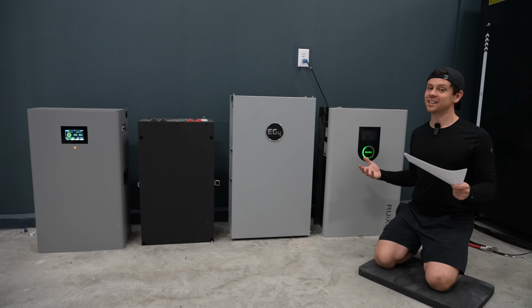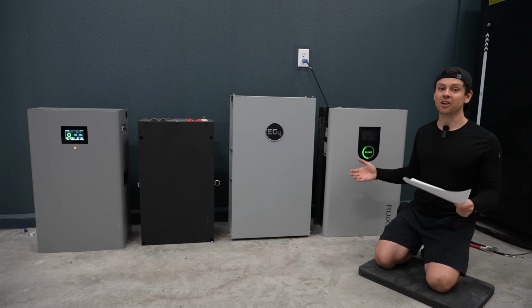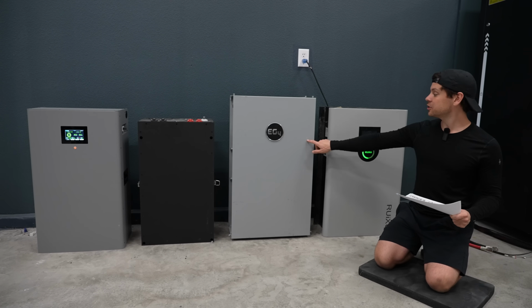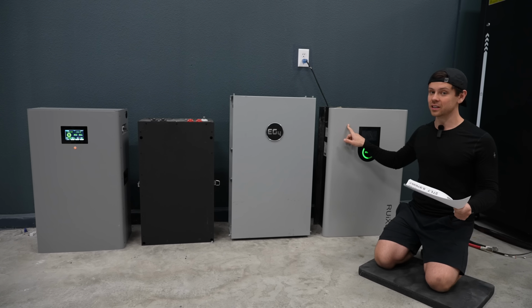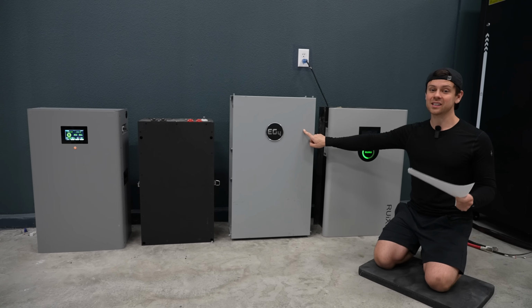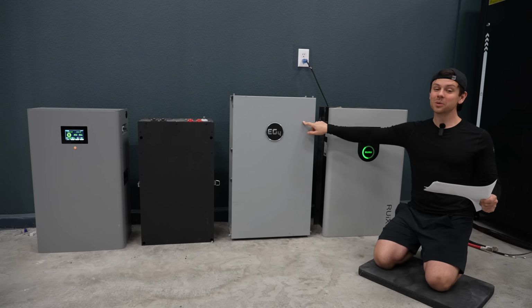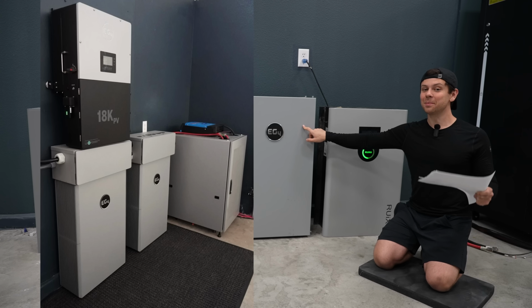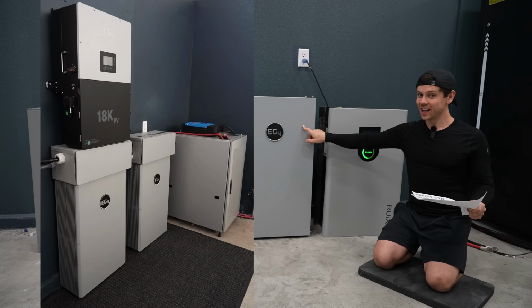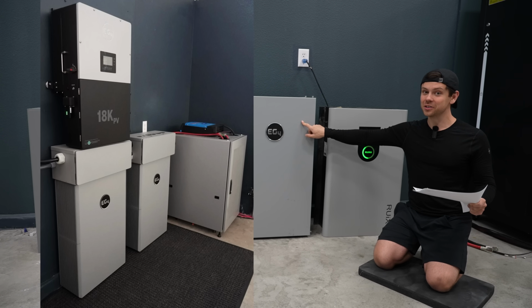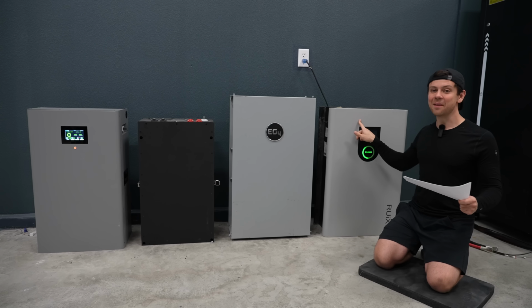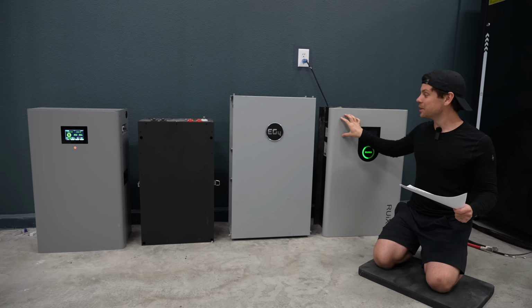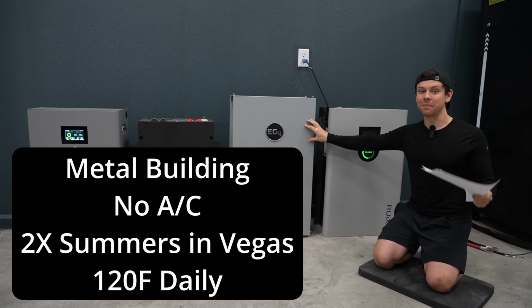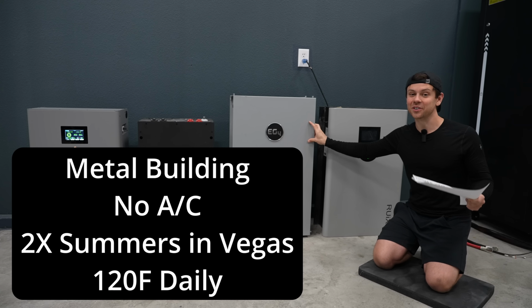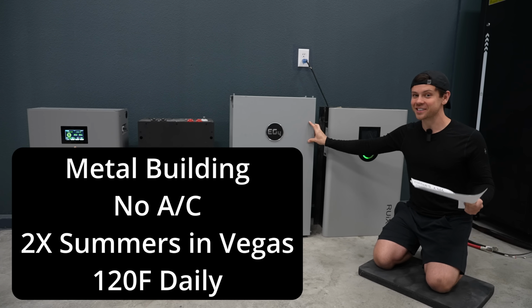First I tested capacity, but these batteries are not the same age. These 2 batteries on the right I've had for 3 years, and this one in particular I cycled like crazy. This one was for my first hybrid system, and I put 12 megawatt hours through it. I did forced charge and discharge cycles like 24/7. This one I barely cycled at all. And then I put them both into a metal building in my backyard in Las Vegas for 2 summers, 2 years non-stop, and I never charged them a single time.